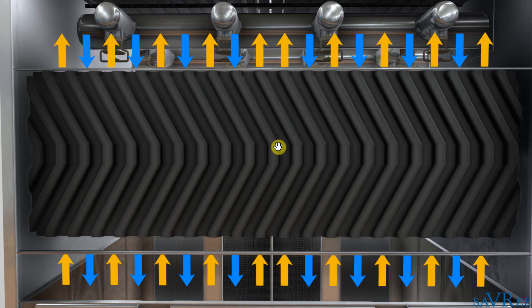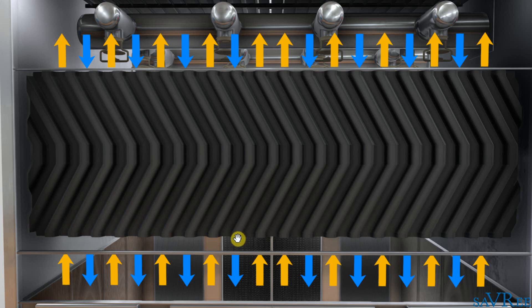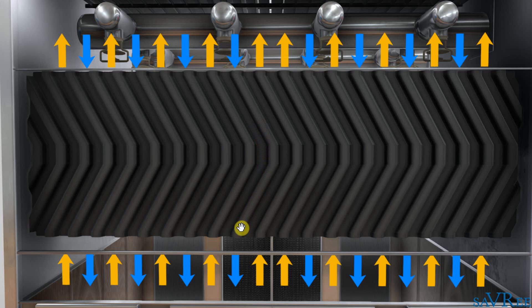Now some people actually believe it is the air passing over the water which cools the water down. This is not strictly true. What we have is about 20% water flowing through the flutes, these items here in the film. And then we have about 80% air flowing up in the opposite direction. Now it's not really the air as such that's cooling down the water. There will be some cooling effect because the air is cooler than the cooling water. However, what's doing the cooling here is evaporative cooling. Some of the water as it's passing through the film is going to evaporate.